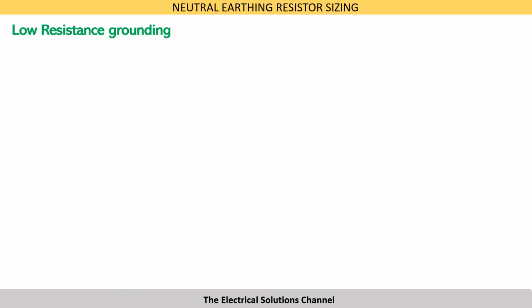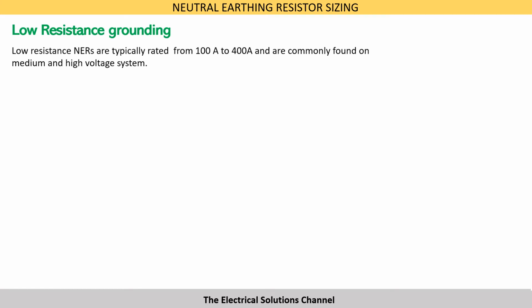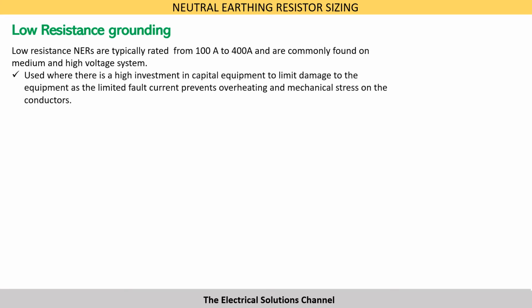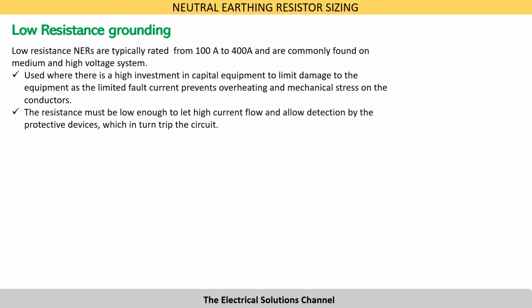Low resistance NERs are typically rated from 100 amps to 400 amps and are commonly found on medium and high voltage systems. These NERs are used where there is a high investment in capital equipment to limit the damage to the equipment, as a limited fault current prevents overheating and mechanical stress on the conductors. The resistance must be low enough to let high current flow and allow detection by the protective devices, which in turn will trip the circuit.